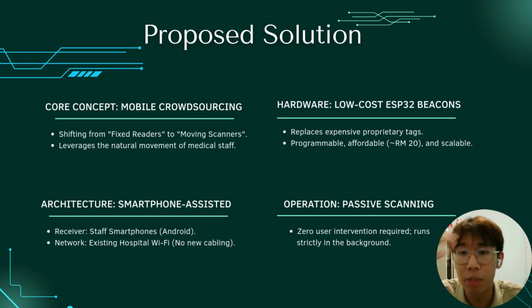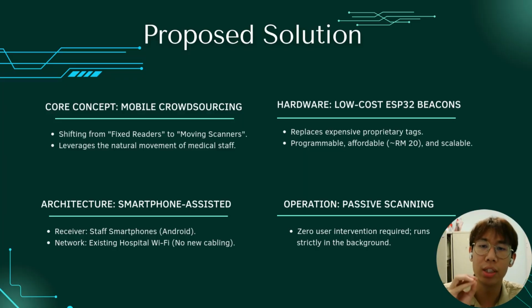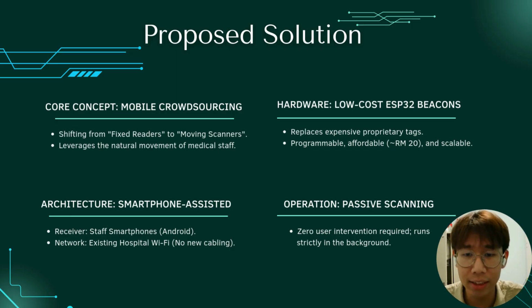So as the staff go about their daily rounds, their phones run a background service that passively listens for these beacon signals. So when the phones detect a ventilator nearby, it captures the signals and uploads them via the hospital's existing Wi-Fi network. Crucially, the system is passive, so the nurse doesn't need to open an app, press a button, or stop what they are doing. The system works autonomously in their pockets, so it requires zero cognitive load from the user. This effectively removes the high capital expenditure barrier and makes asset tracking accessible for public hospitals.